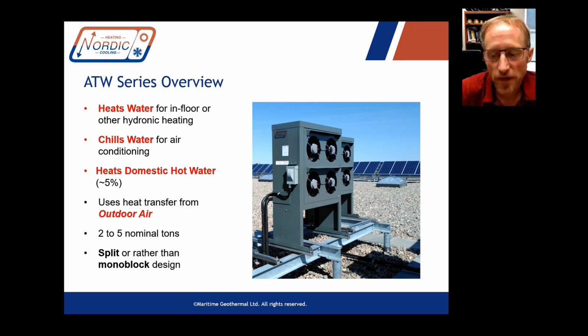Okay, that's with air source heat pumps? With air source heat pumps. I just had an energy modeler come back and tell me that, for the new climate data, the current climate weather file, our backup actually didn't turn on, because the building kind of surfed over those worst case hours. Interesting, the thermal mass in the building. And we were using a larger air mech unit for that. It's like a great big office building.